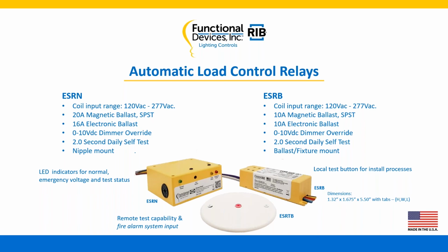So what we're moving into is a newer feature. We came out a few years back with this one. It's an automatic load control relay, our ESRN and ESRB. Two different models, as I showed earlier, one for the plenum, one for the ballast, and of course the ESRTB, the test button. You'll notice these coil input voltages, 120 through 277, are both universal voltage, so they fit right in. The ESRN is a 20 amp magnetic ballast, single pole, single throw with a 16 amp electronic ballast. Over on the ESRB side, we've got a 10 amp magnetic ballast, single pole, single throw with a 10 amp electronic ballast. Both have the 0 through 10 volt dimming override. Both have the 2-second daily self-test included. The ESRN is nipple mounted. The ESRB is ballast or fixture mounted.